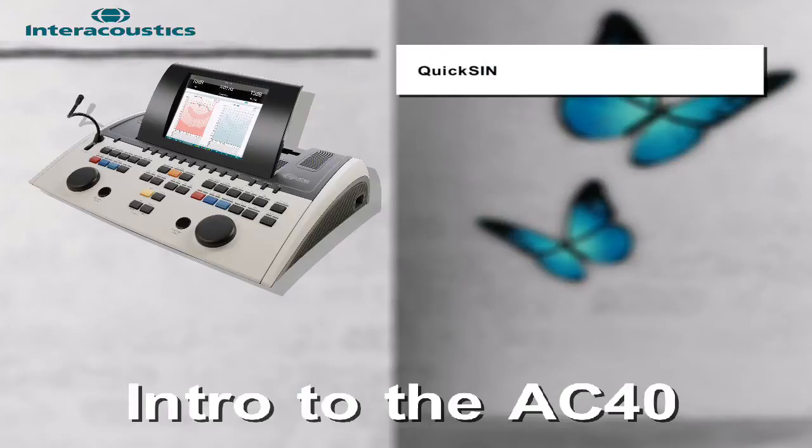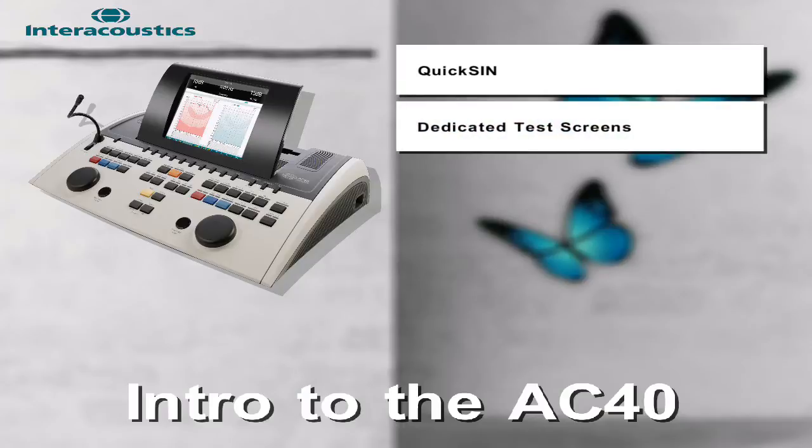The QuickSIN is loaded directly on the device, so an external CD player is not required. The AC40 offers a wide range of pre-programmed and dedicated testing screens which include TEN, Hughson-Westlake, Master Hearing Aid, Hearing Loss Simulator, and more.